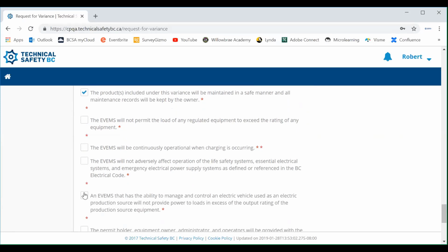The EVEMS will not allow the load of any regulated equipment to exceed the rating of any equipment. So we want to make sure we're not overloading any circuits, and of course that goes back to Section 8 of the code, so we'll ensure the system falls under those parameters.